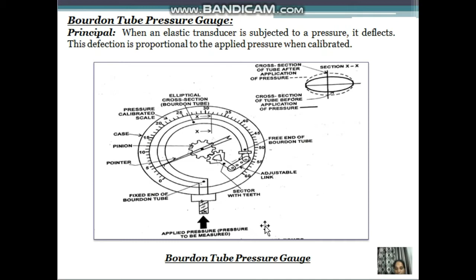So the Bourdon tube tends to deflect; it was actually in a circular arc shape, and it tends to straighten. This causes a displacement at the free closed end of the Bourdon tube, and this displacement is proportional to the applied pressure. As the free end of the Bourdon tube is connected to the link, sector and pinion arrangement, the displacement is amplified and converted to a rotary motion of the pinion. As the pinion rotates, it makes the pointer assume a new position on a pressure calibrated scale to indicate the applied pressure directly. As the pressure in the case containing the Bourdon tube is usually atmospheric, the pointer indicates gauge pressure. This is how the Bourdon tube works.